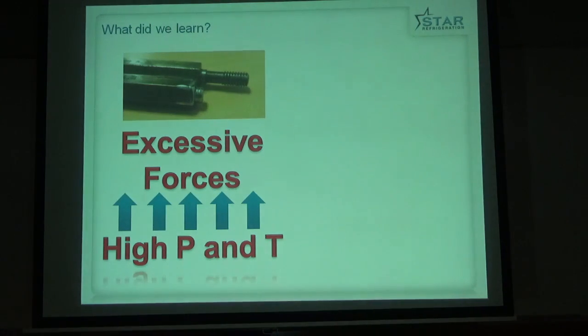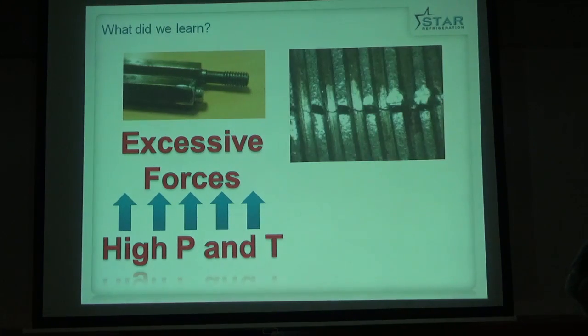Also, other components highly stressed. This is a push rod that moves the slide valves in the compressor, before and after, fractured because of the high forces. So we're using a strengthened push rod. This is a tube from one of the shell and tube condensers. It's a finned tube, and there was a defect in the material. So the tube was faulty.